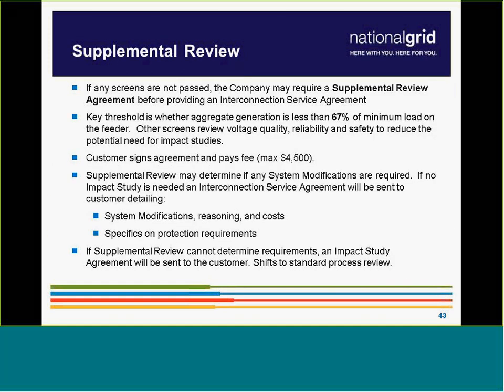So then, to explain a little more about the simplified review process: as mentioned before, there's an agreement and payment. One of the key things they look at is aggregate generation less than 67% of minimum load on the feeder, and also voltage quality, reliability, and safety. Those are the types of things we look at. The fees for that — the maximum we can collect is $4,500.